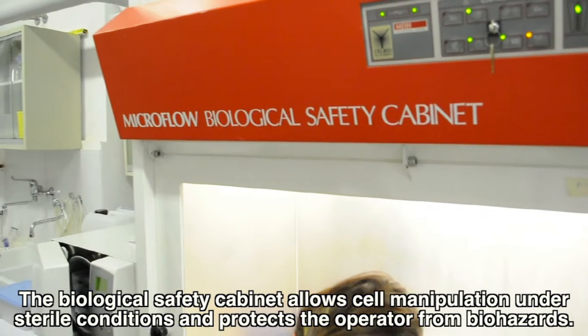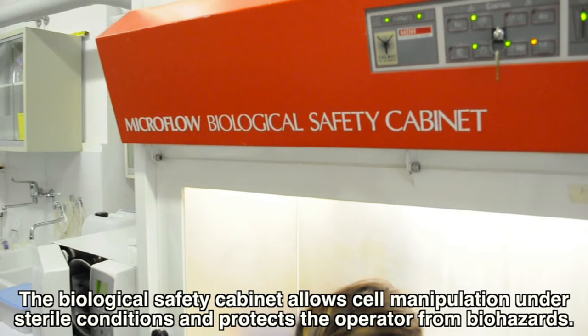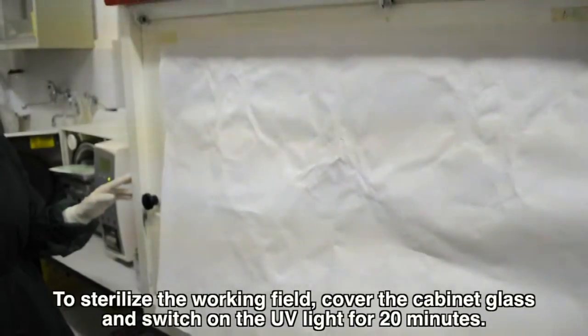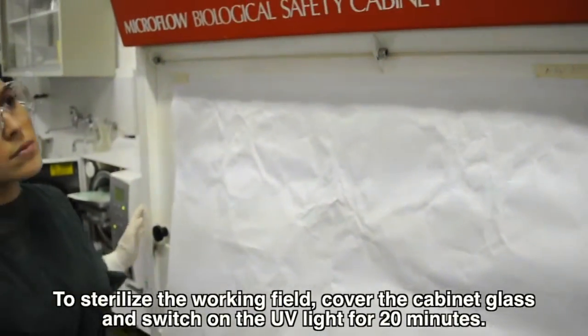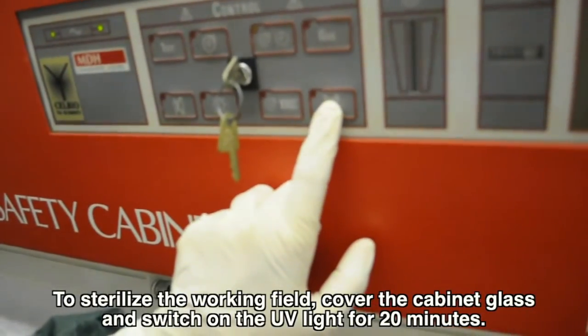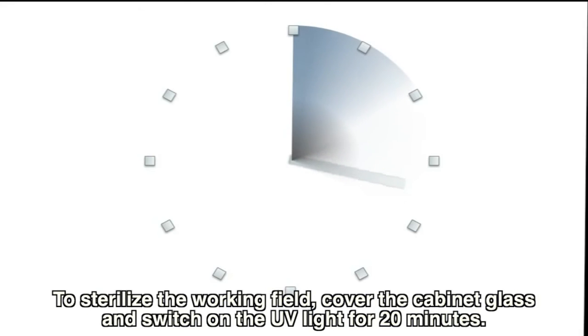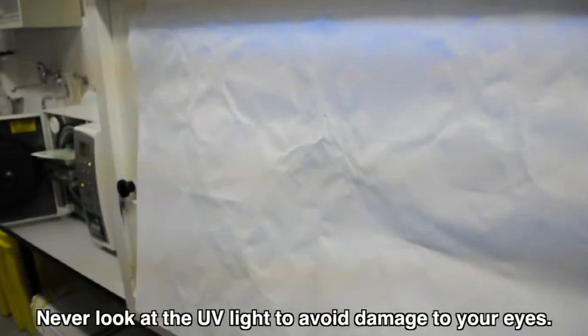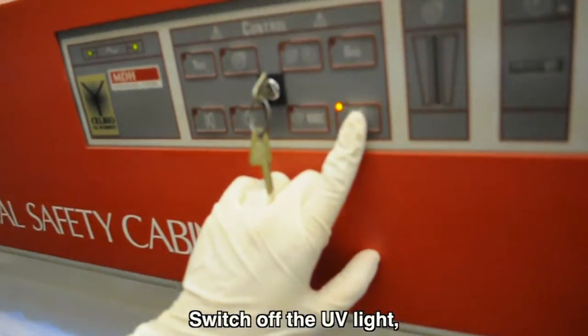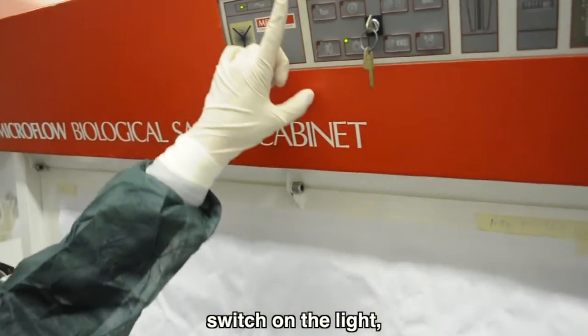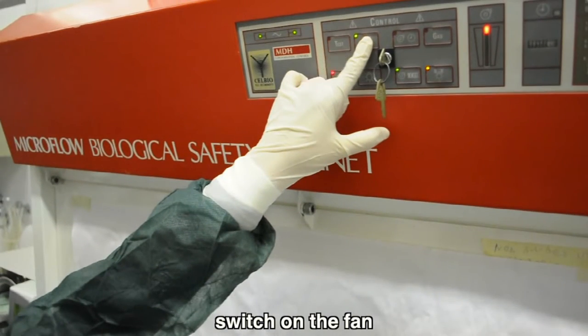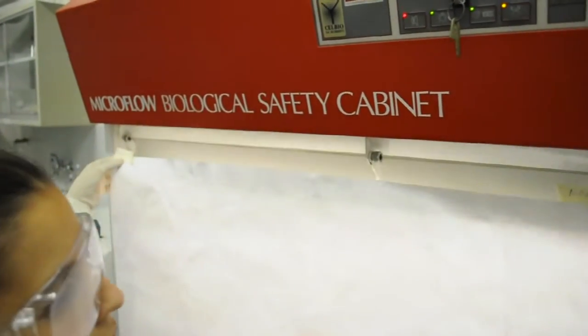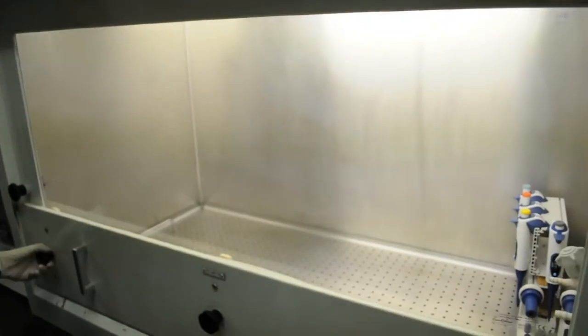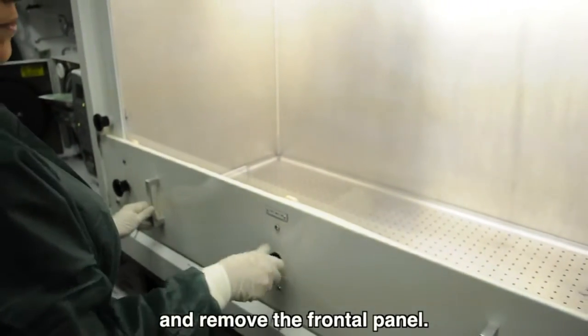The biological safety cabinet allows cell manipulation under sterile conditions and protects the operator from biohazards. To sterilize the working field, cover the cabinet glass and switch on the UV light for 20 minutes. Never look at the UV light to avoid damage to your eyes. Switch off the UV light. Switch on the light. Switch on the fan. And remove the frontal panel.